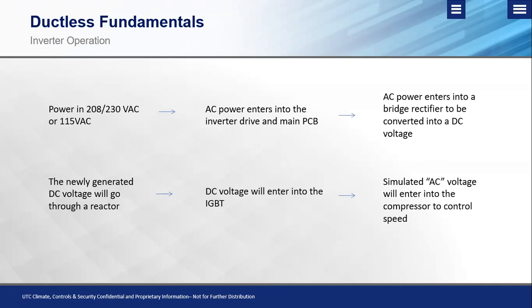Now, the biggest difference between an inverter compressor and a non-inverter or a staged compressor, whether you have two stages or a single stage, is going to be the fact that we have that nice slow start with these inverter compressors. So if you think back to the HVAC basics or your fundamentals, you think of a fixed speed compressor and you have a contactor, whether it's single stage or two stage. If it's a two-stage piece of equipment, you have your first stage, which is compressor one, gets the call, pulls in, and runs. And typically, the most amount of current seen is going to be on that initial start when we power that compressor. That's going to be the peak amount of amperage, or the amount of power, or the amount of money that you're paying to run the equipment. However, when we go into the inverter-based operation, because we have that slow start and we don't have that initial inrush current, we're drawing less power, in turn saving more money.